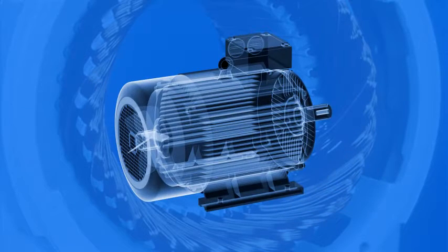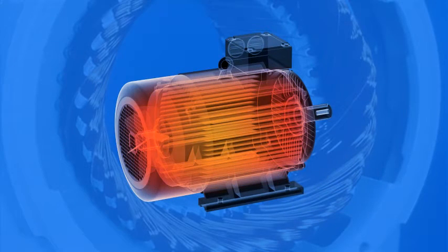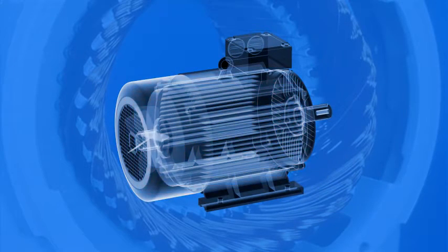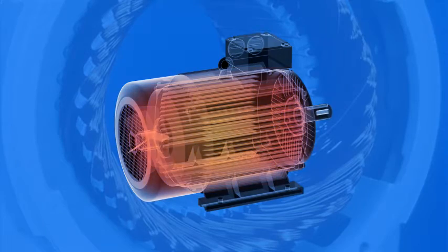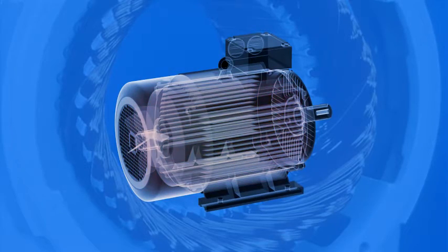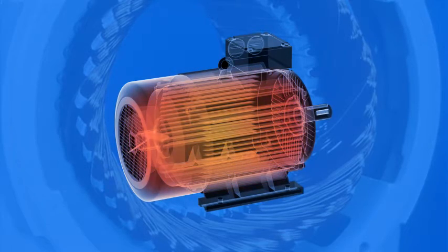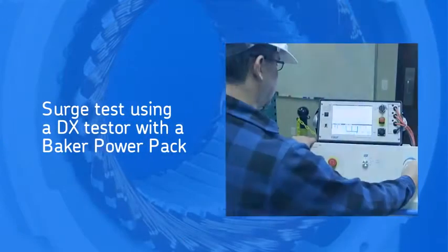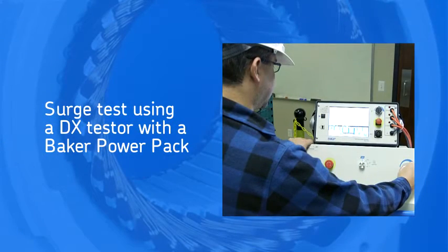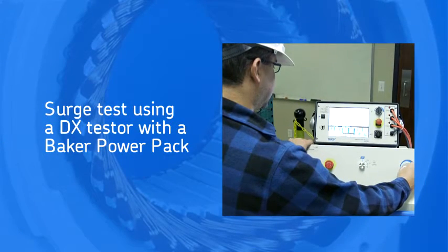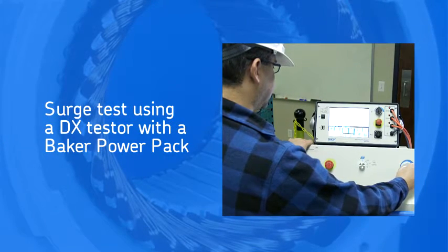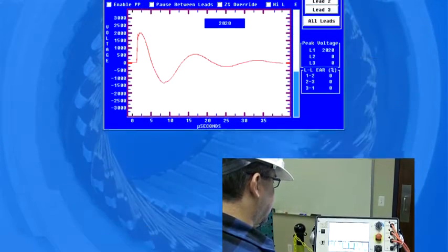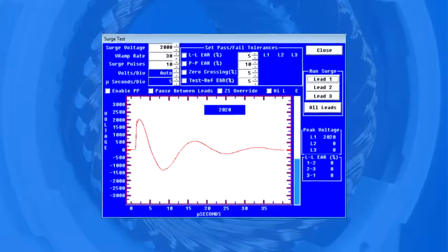When this fault occurs, the motor will draw a lot of current, quickly overheat, and can melt down in minutes. The surge test can reliably find the strength of turn-to-turn insulation, giving you early warning about when the insulation is weak.